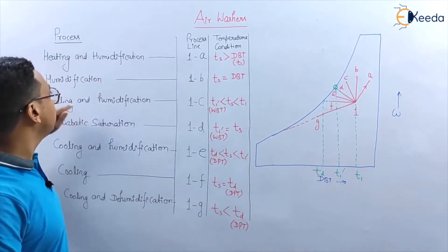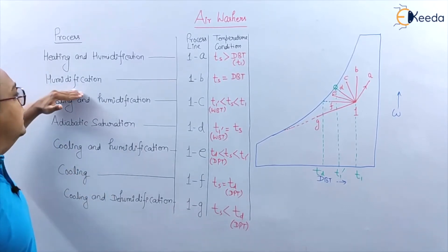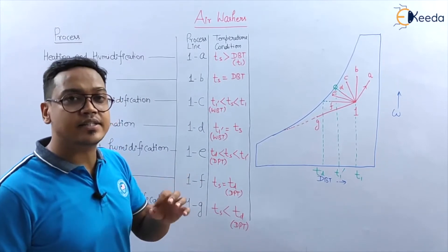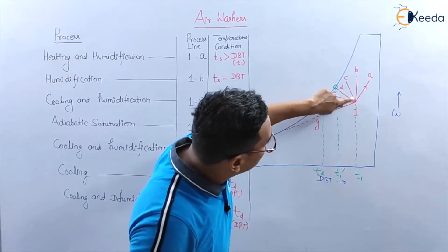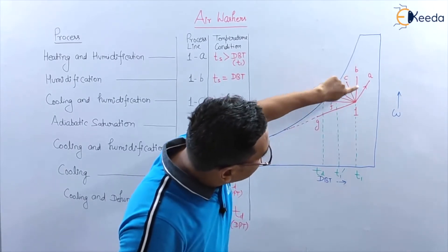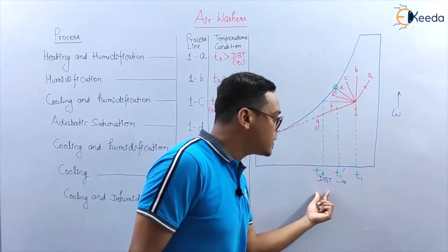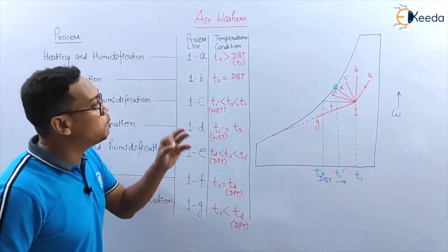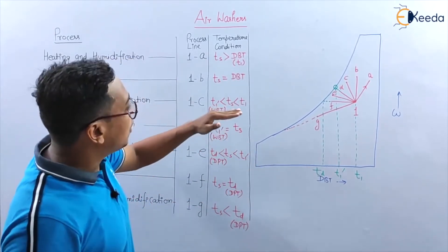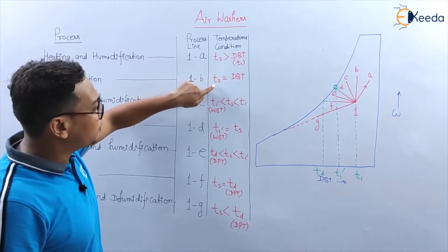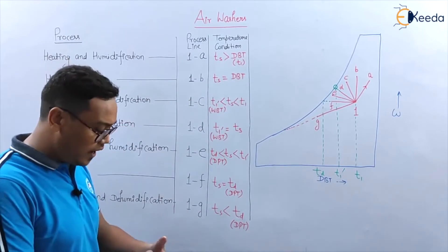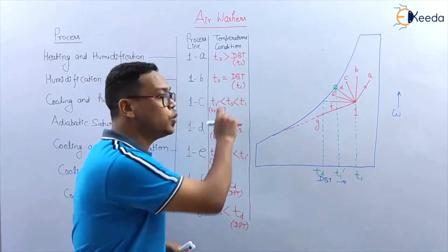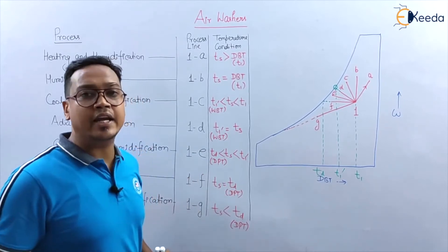Now let's see the second process: humidification. Humidification occurs at constant dry bulb temperature — process 1 to B. At constant temperature, only moisture will increase in the air. The condition for this case is that the surface temperature of water should be equal to the dry bulb temperature T1 of the inlet air.